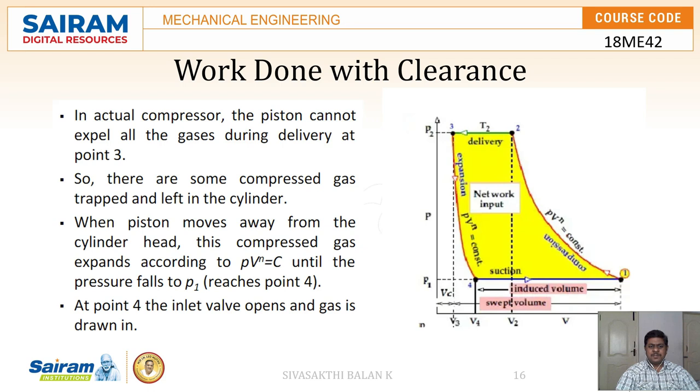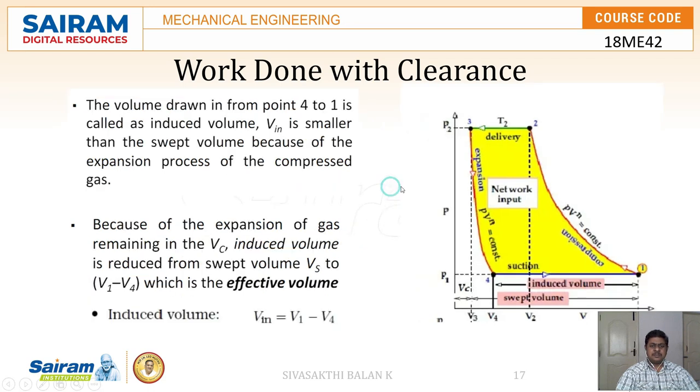At point 4, the inlet valve opens and gas is drawn in, that means gas is induced inside the cylinder. The volume drawn in from 4 to 1 is called the induced volume. It is always smaller than the swept volume. The swept volume is the volume between V3 and V1, and the induced volume is the volume between V4 and V1.